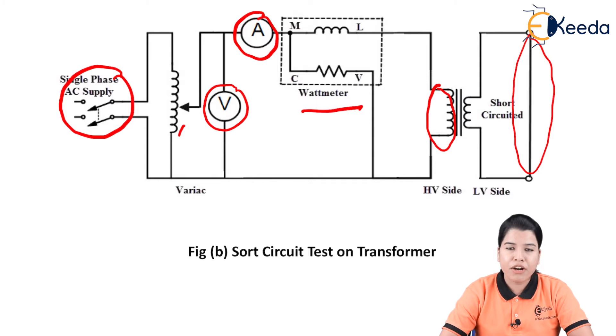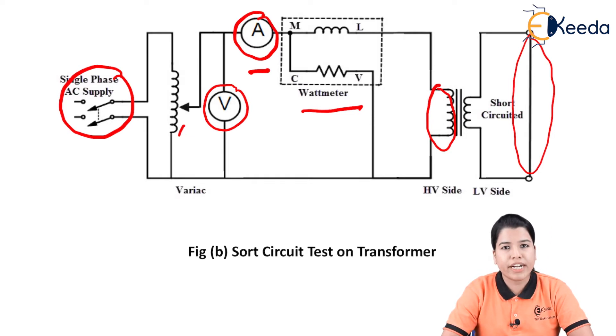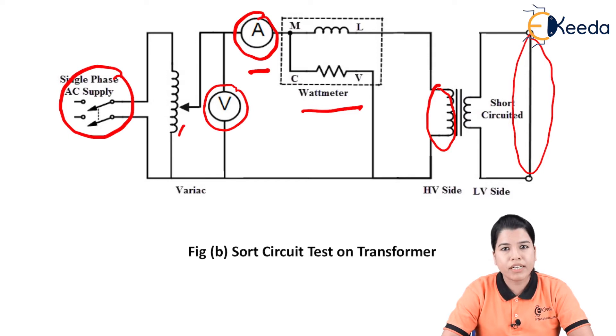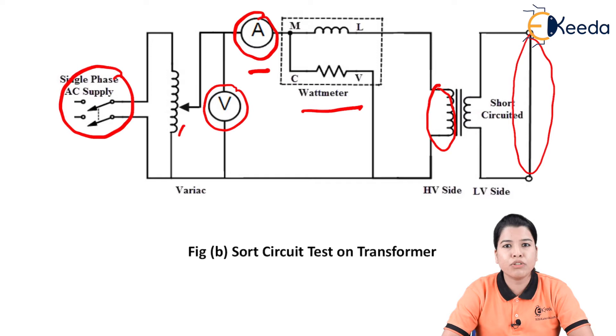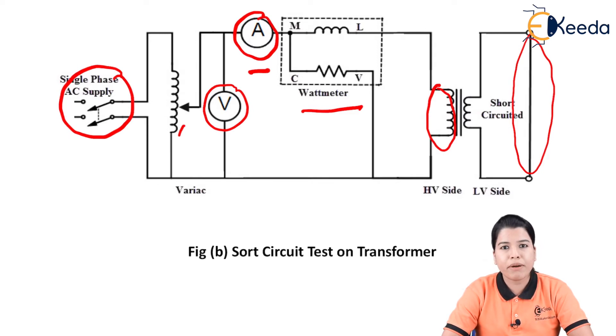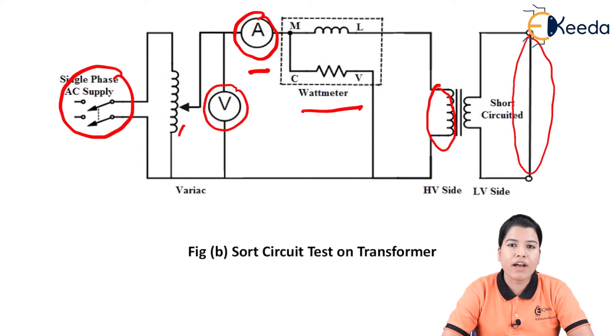The procedure for the short circuit test is: first find the rated primary current, then vary the voltage until the ammeter gives the rated current value. This voltage is very small compared to the rated primary voltage. Since the voltage is very low, the iron losses can be neglected. The transformer only shows copper loss, which is directly proportional to current.